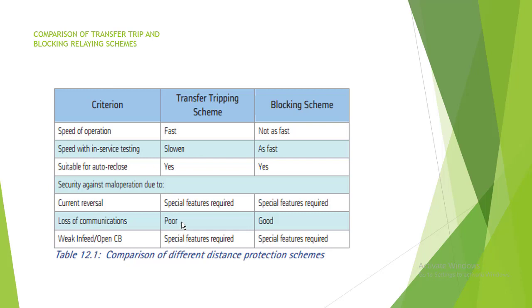Loss of communication: in the transfer tripping scheme, if communication is lost, performance is very poor — it cannot work. In the blocking scheme, if communication is lost, it can still work — performance is good.